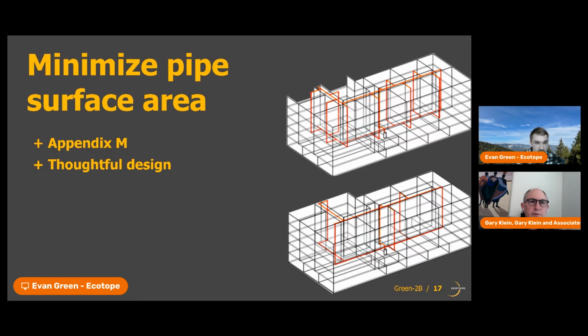So if you look at these pictures of two buildings on the right here, you can see they're the same buildings with the same number of units in them, but the building up top here has a lot more hot water risers. You can see the water travels from the water heater and up these risers and then back to the return line, which returns back to the water heater. So a pretty typical design.